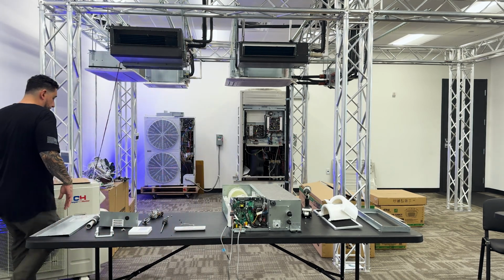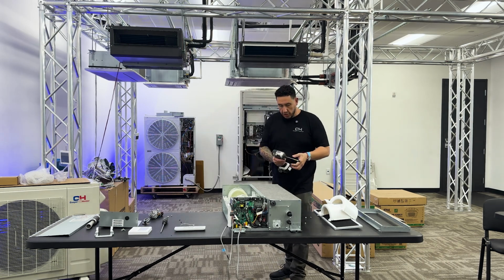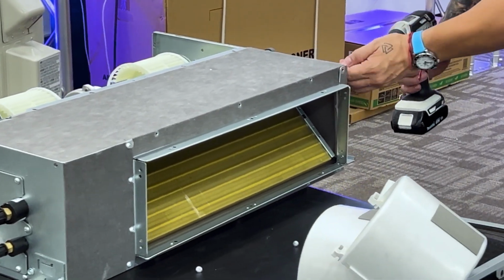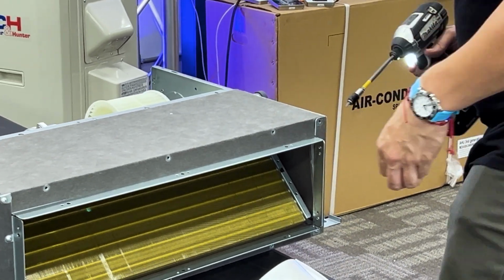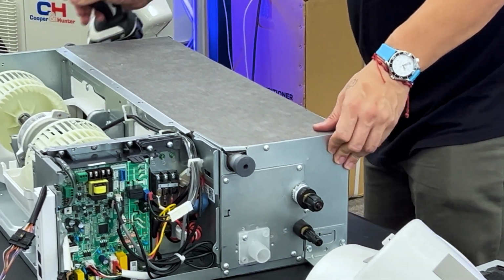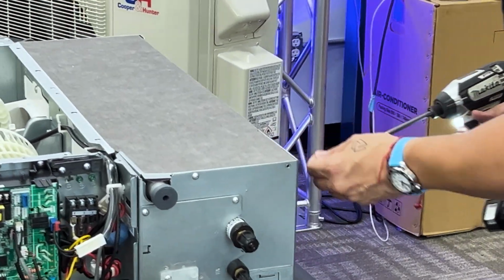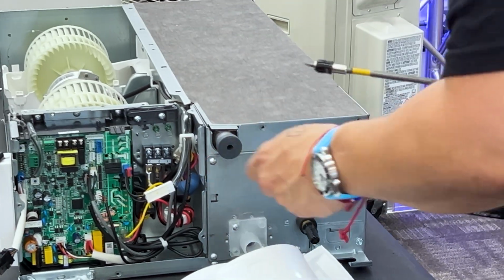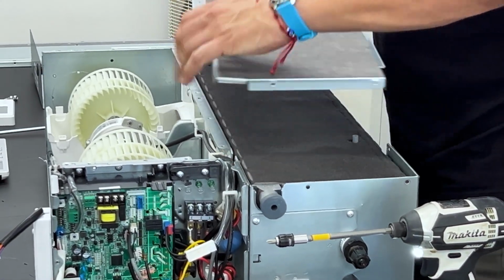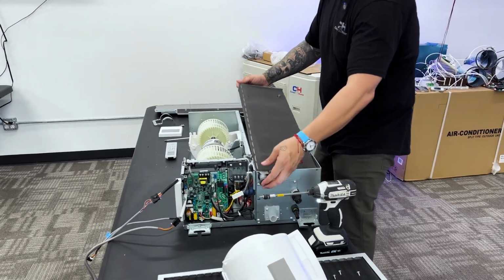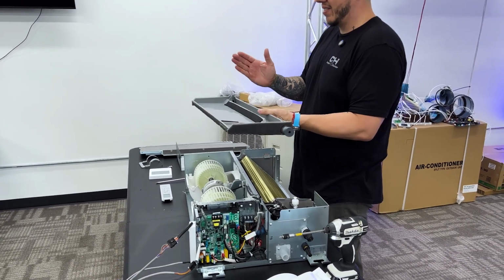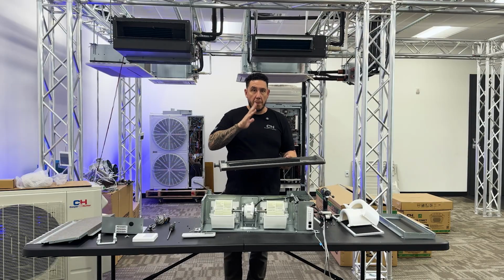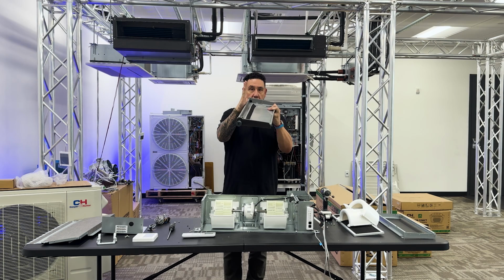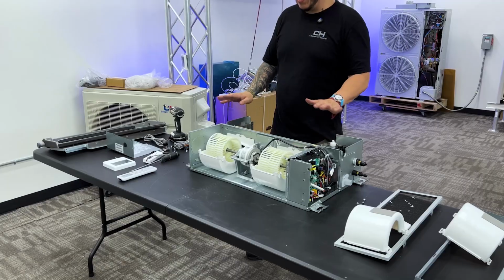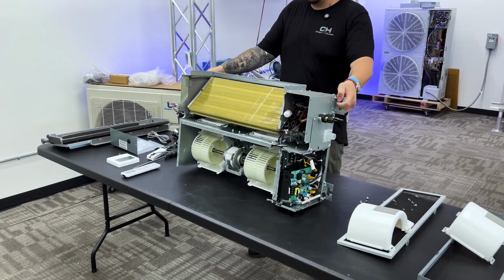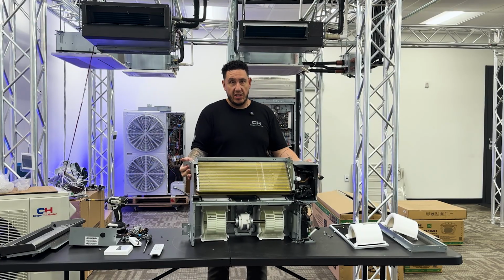But on our larger units, we do have larger drain pans in them. We have an L-shaped drain pan in our 24, 36, and 48,000 BTU units, which allow us to modify how they can be installed. So with those units, I've removed this panel here, so that way I could show you. Here's what my drain pan looks like on my 6, 9, 12, and 18,000. On my 24, my 36, and 48, I have an L-shaped drain pan. So what that allows me to do with those units, I could have it installed horizontally, or I could have it installed vertically. With that L-shaped drain pan, it'll catch all the condensation on the inside.